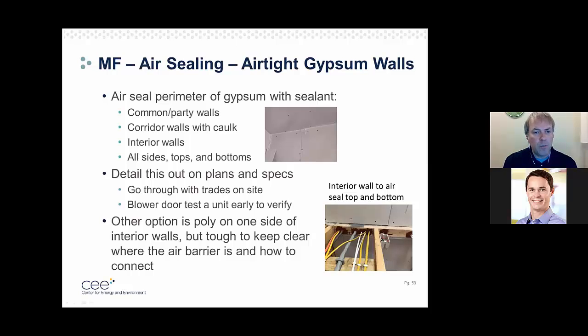So one other option we've seen done before is poly on one side of the interior walls. It works and can provide a tight air barrier and eliminate some of the sealing, but we've been talking to tradespeople doing both ways, and they prefer the sealed drywall approach. The poly just gets kind of confusing - where do you lay it, which side of the wall assembly? You really don't want to put it on both sides - if you have moisture ever trapped in there, that could lead to moisture issues, rotting, or mold. So just one side would be ideal if you're going to do that. But I'd recommend just a sealed gypsum board as a good air barrier to make these units nice and tight.